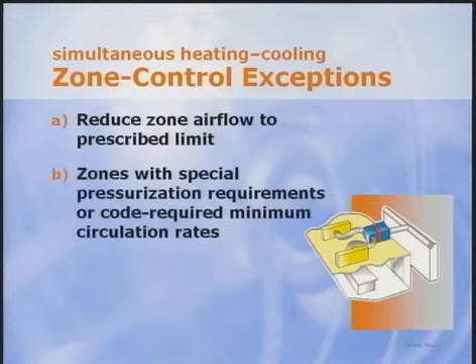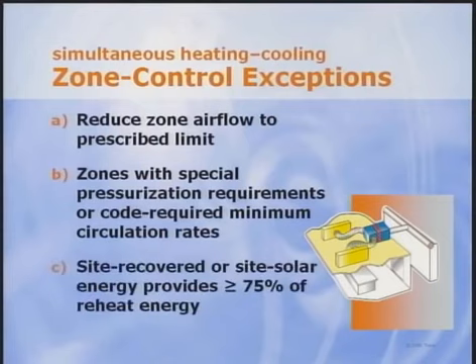Next, the restriction on simultaneous heating and cooling does not apply to zones with special pressurization requirements or code-required minimum circulation rates. Both of these may occur in healthcare facilities. You may do any amount of reheating if at least 75% of the reheat energy is site recovered or site solar. Again, this could be directly from refrigerant in the form of hot gas reheat or from the condenser water of a water-cooled system. Now, let's look at the zone airflow limits allowed.